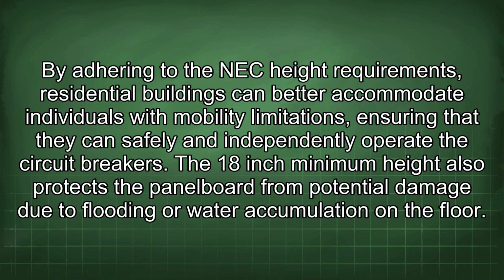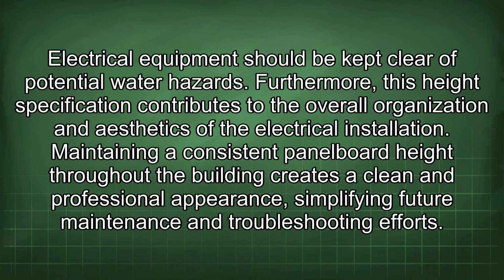The 18-inch minimum height also protects the panel board from potential damage due to flooding or water accumulation on the floor. Electrical equipment should be kept clear of potential water hazards. Furthermore, this height specification contributes to the overall organization and aesthetics of the electrical installation. Maintaining a consistent panel board height throughout the building creates a clean and professional appearance, simplifying future maintenance and troubleshooting efforts.